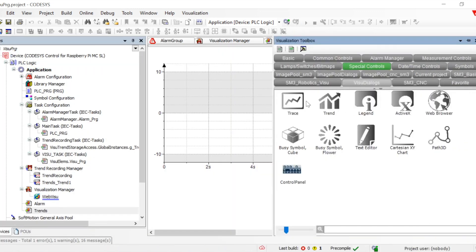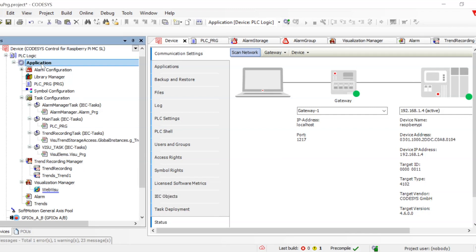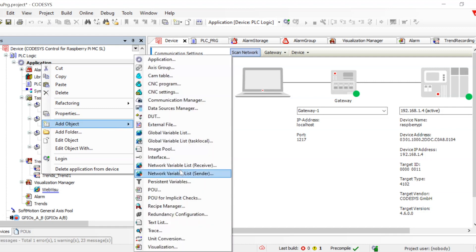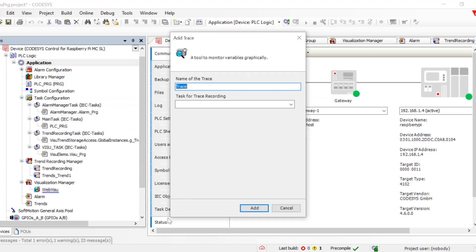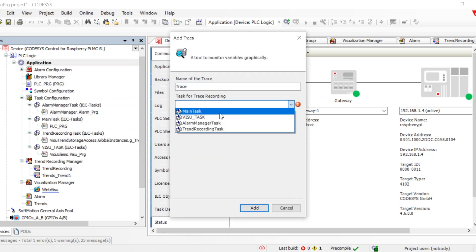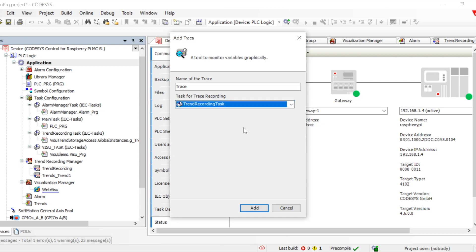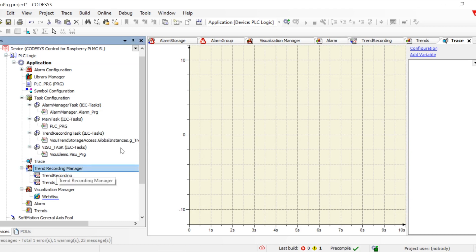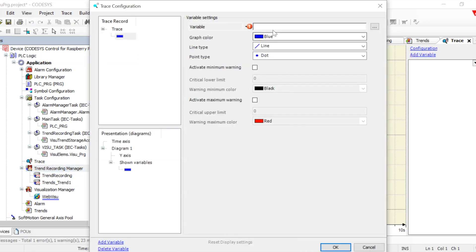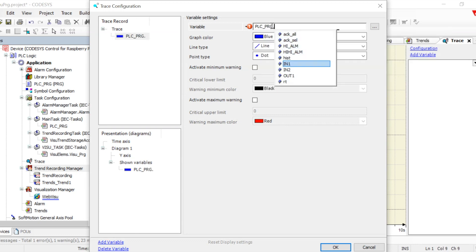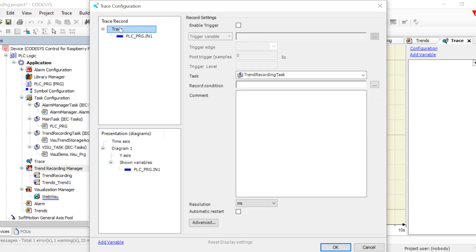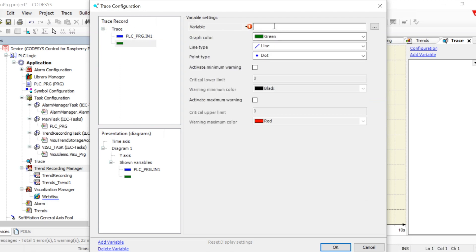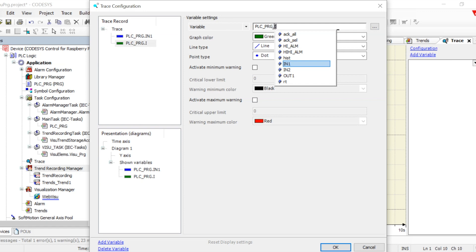That was all about trends. We also have another option called Traces. To add traces: go to Add Object, go to Traces, click on it, and then assign a task for the trace recording — we can take any task and assign the traces to it. Traces are basically for seeing changes happening in the millisecond time frame, unlike trend recording. It won't have date details but will show all the changes, and we have the option to choose in what millisecond interval we want to plot the traces.